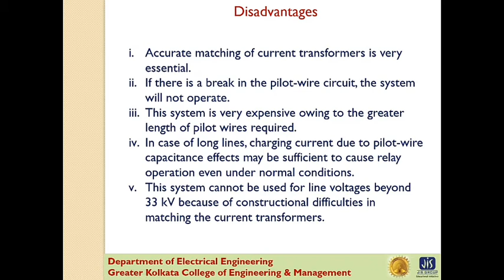Next is the Translay system. Now this system is similar to voltage balance system except that here balance or opposition is between voltages induced in the secondary winding, wound on the relay magnet, and not between the secondary voltages of the line current transformers. Now this permits the use of current transformers of normal design and eliminates one of the most serious limitations of the original voltage balance system, namely its limitation to systems operating at voltage not exceeding 33 kV. The application of Translay scheme for a single phase line has already been discussed in our previous video.